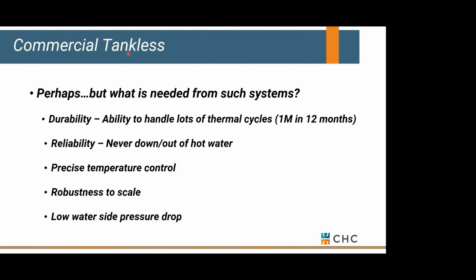And the reason commercial is so hard is that you get a lot of cycles. Picture a kitchen that's on and off all the time, all day long, and you've got no storage tank to kind of buffer that out. So your heater has to handle all those cycles that are occurring within the building. You can have up to 1 million cycles a year in a typical commercial water heating application. So you have to have a pretty resilient system if you're going to go after that.